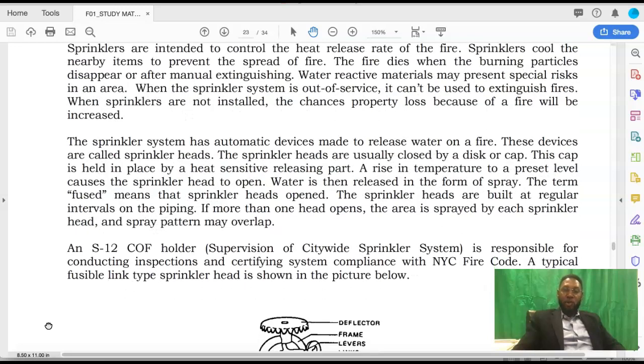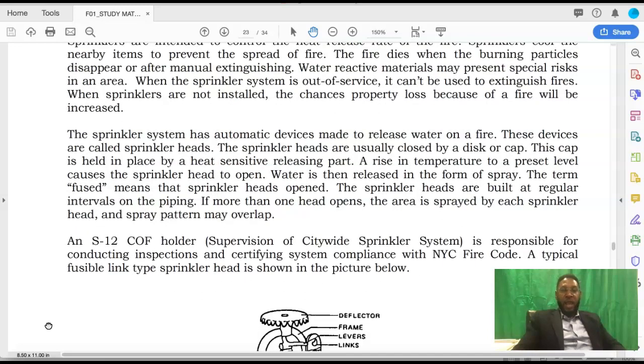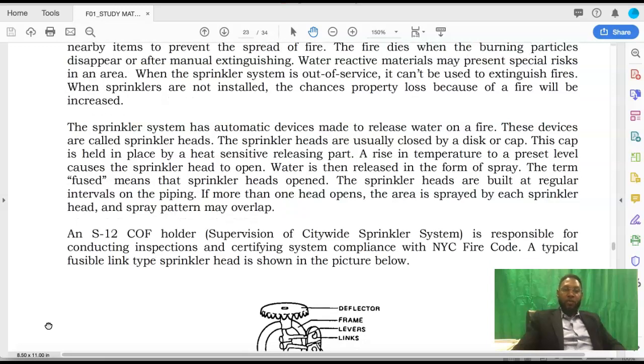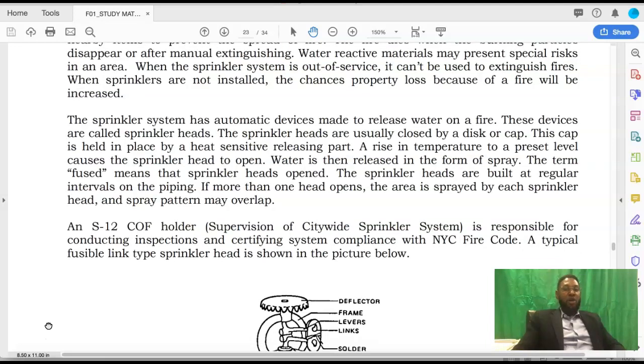Water reactive materials may present special risk in any area. When the sprinkler system is out of service, it cannot be used to extinguish fire. When sprinklers are not installed, the chance of property loss becomes very high. So that's why now you need a fire guard. That's why you need a fire guard when it's out of service.